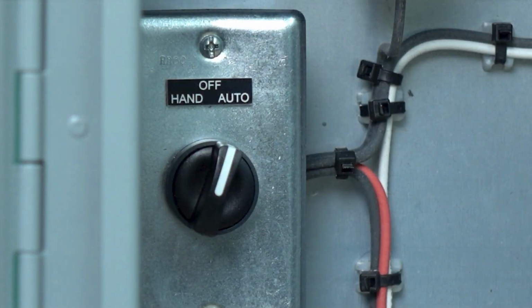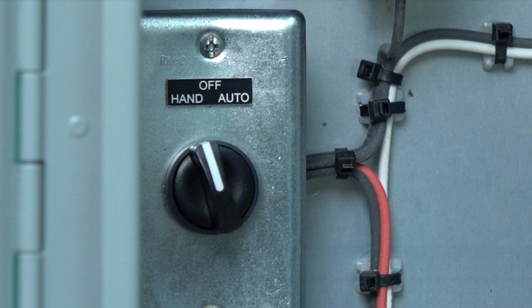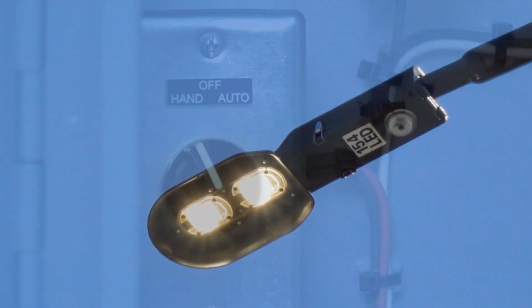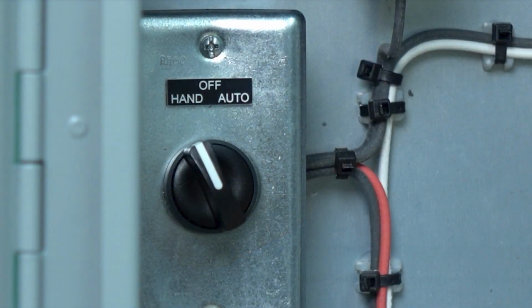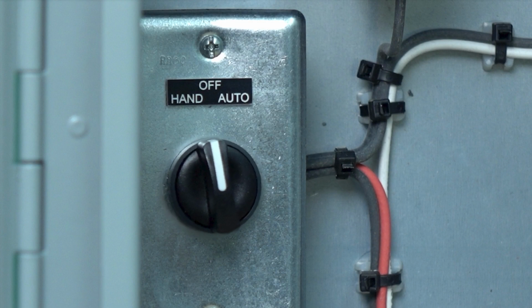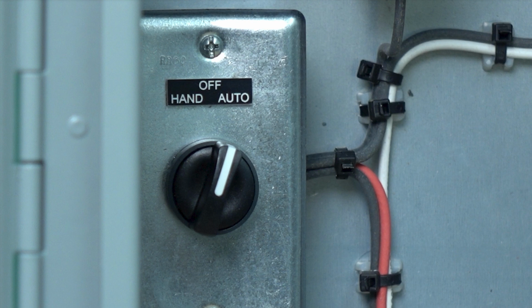The hand-off-auto switch controls both the manual and nighttime automatic operation of the lighting contactor. When power is on at the service, the inspector should turn the switch to the hand position. All lights fed by the service should come on. Upon completion of this inspection task, the switch should be returned to the auto position so that the photocell will automatically control the lights to come on at night and turn off during the day.